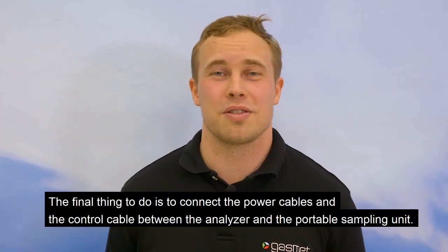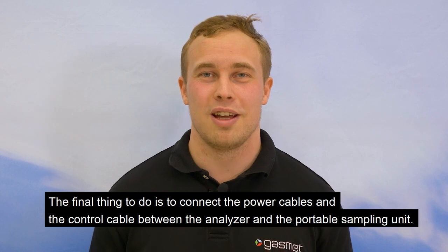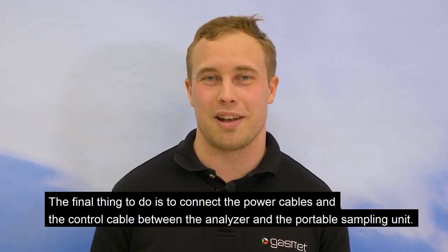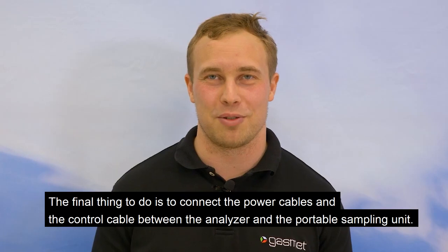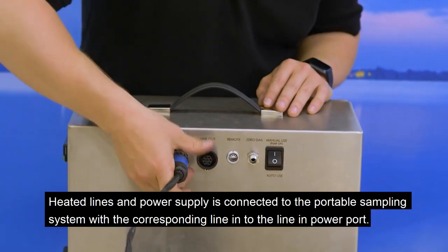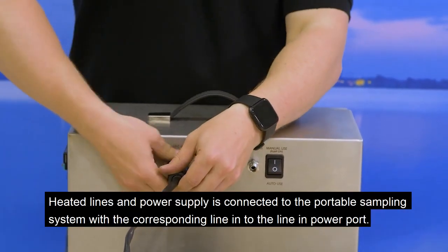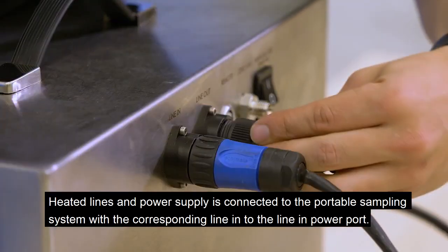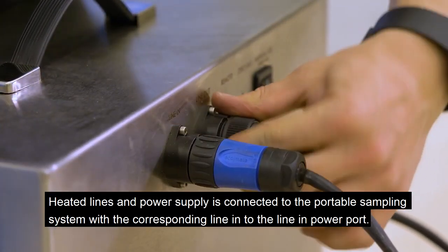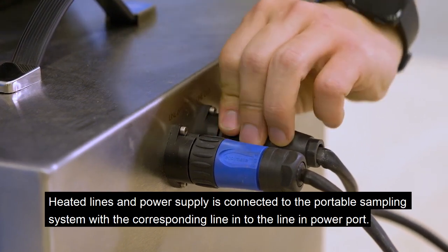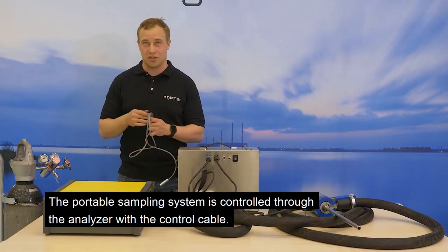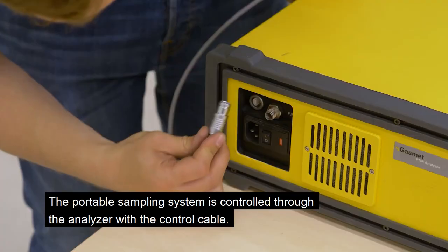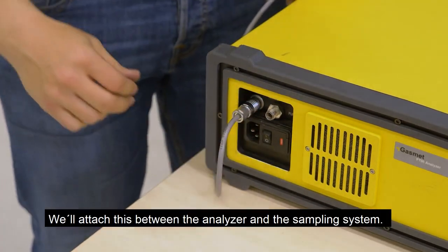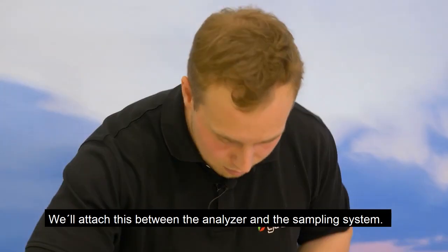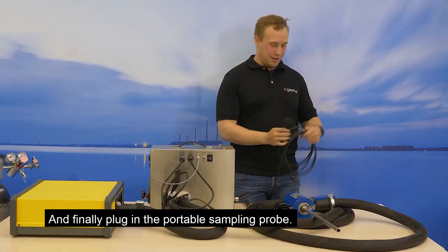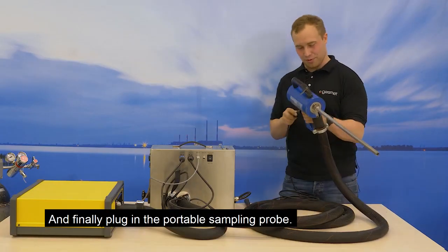The final thing to do is to connect the power cables and the control cable between the analyzer and the portable sampling unit. Heated lines power supply is connected to the portable sampling system with the corresponding line in to the line in power port. The portable sampling system is controlled through the analyzer with a control cable. We'll attach this between the analyzer and the sampling system. And finally plug in the portable sampling probe.